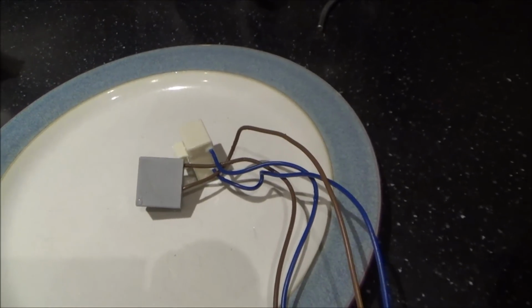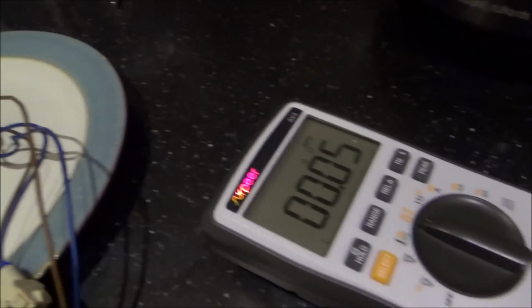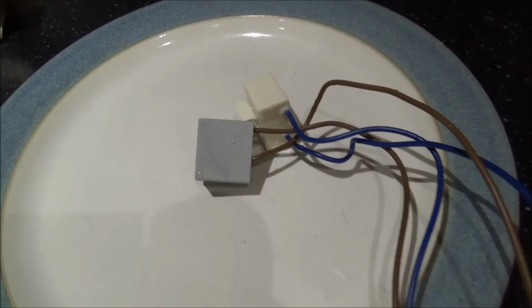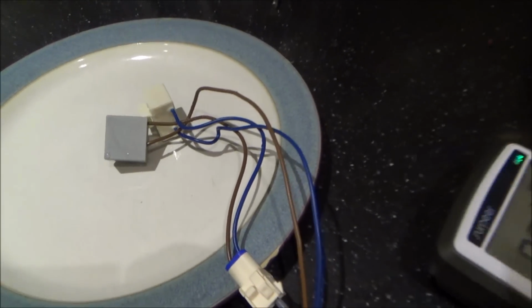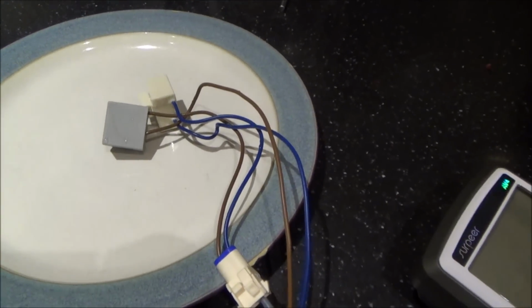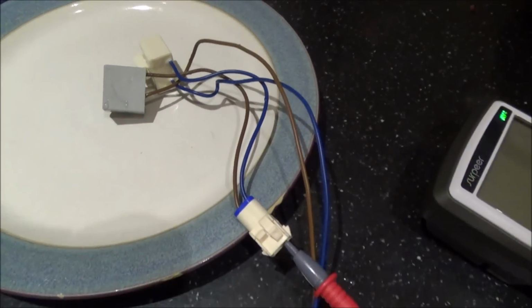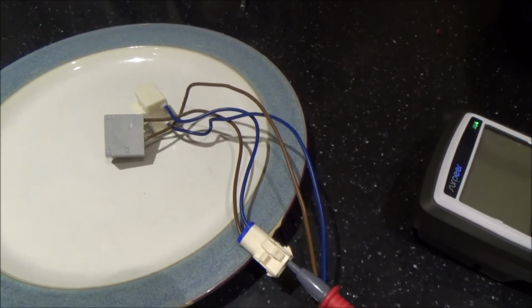Okay, and now as you can tell from my meter, there is continuity on the blue one. So obviously the temperature's gone below, I presume, 40 degrees C, and now it's kicked in. So now I'm going to try to freeze this grey one, and that will tell me whether this is faulty or not. Remember, this was my original lead that I presumed was faulty, but maybe it's not.